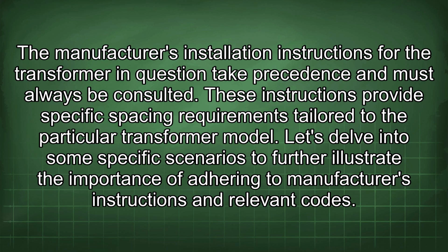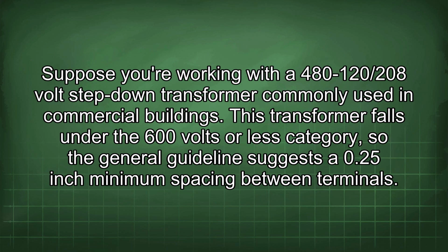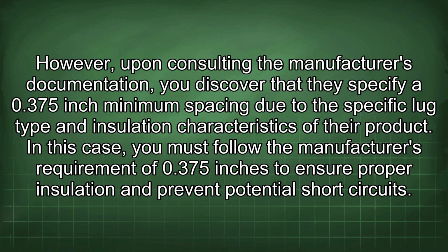Let's delve into some specific scenarios to further illustrate the importance of adhering to manufacturer's instructions and relevant codes. Suppose you're working with a 480-120/208 volt step-down transformer commonly used in commercial buildings. This transformer falls under the 600 volts or less category, so the general guideline suggests a 0.25 inch minimum spacing between terminals. However, upon consulting the manufacturer's documentation, you discover that they specify 0.375 inch minimum spacing due to the specific lug type and insulation characteristics of their product. In this case, you must follow the manufacturer's requirement of 0.375 inches to ensure proper insulation and prevent potential short circuits.